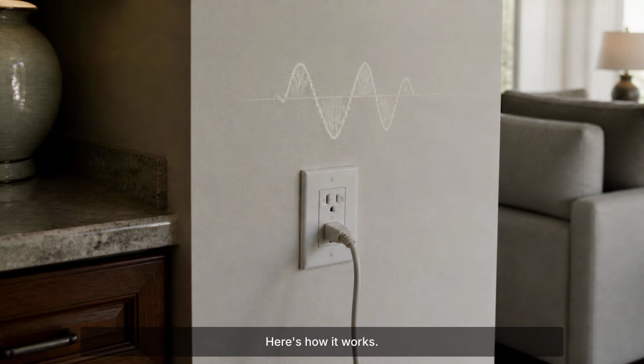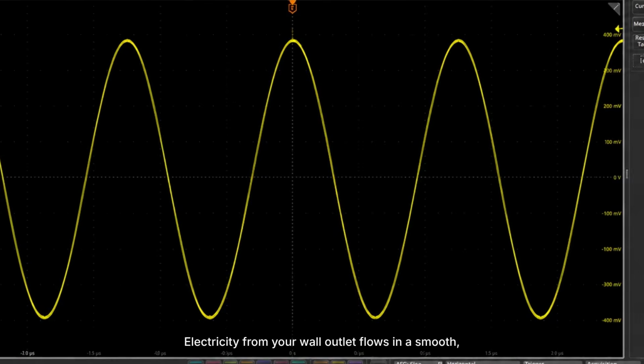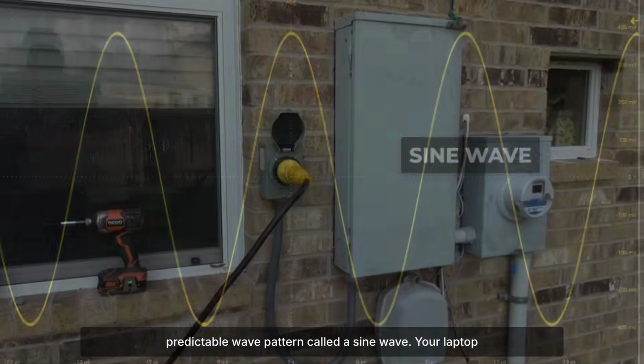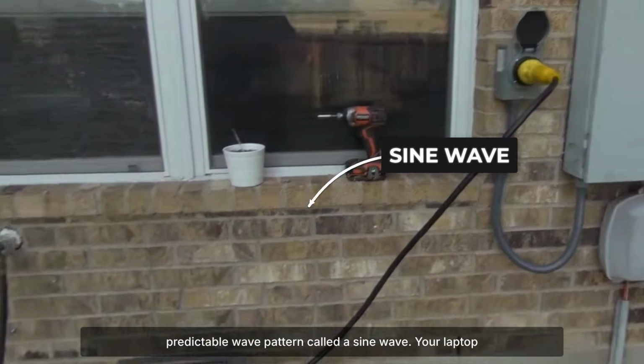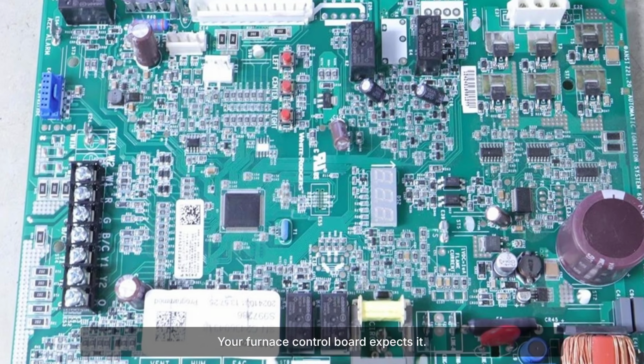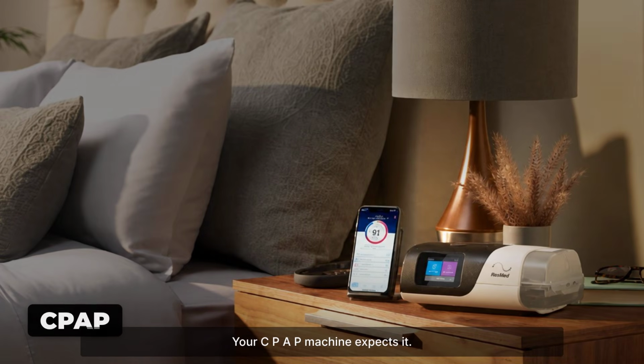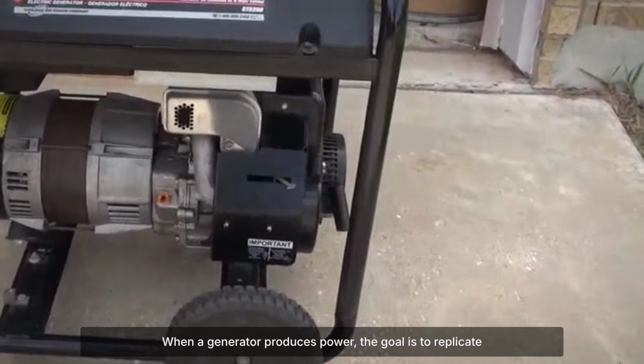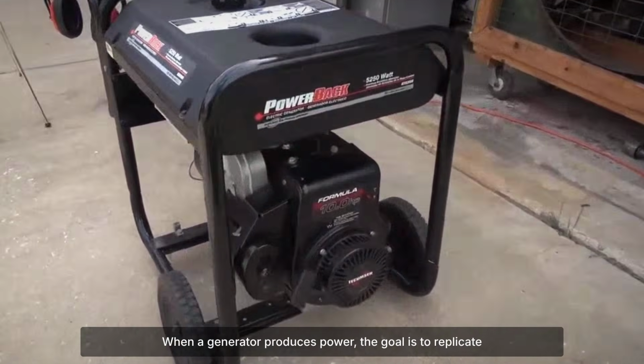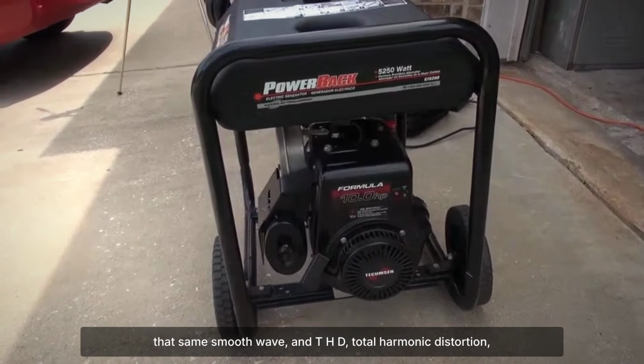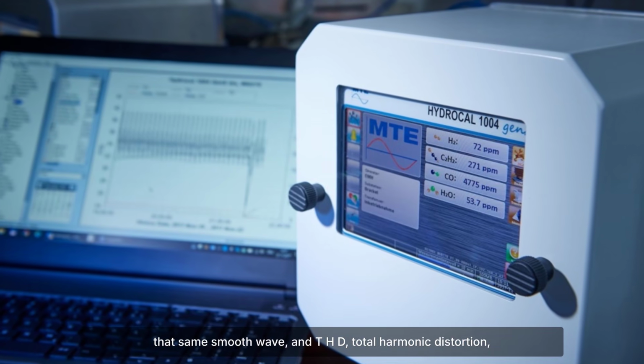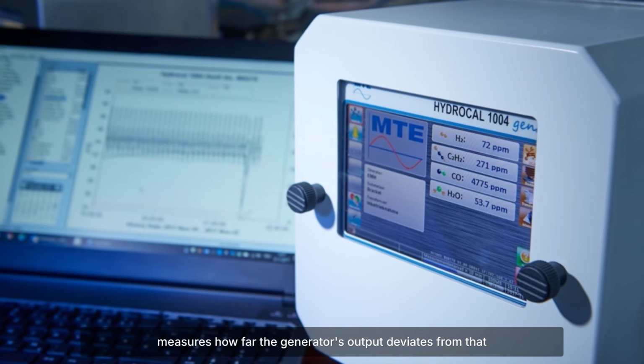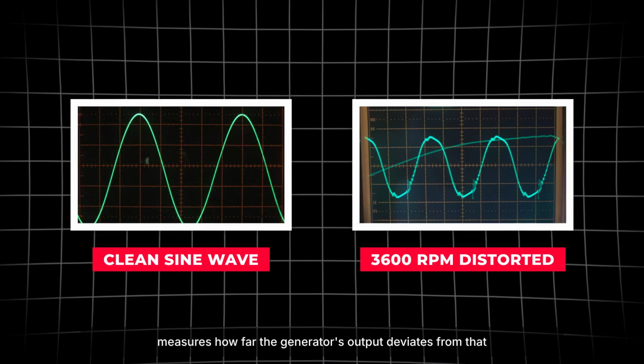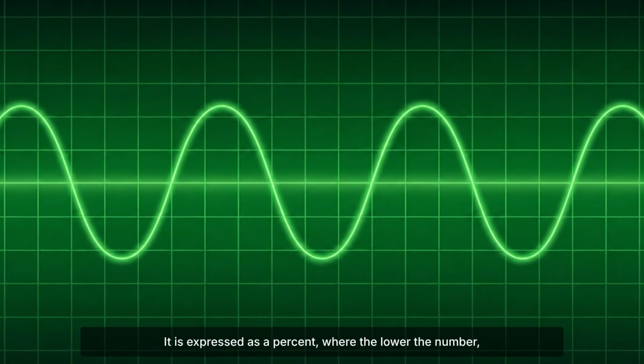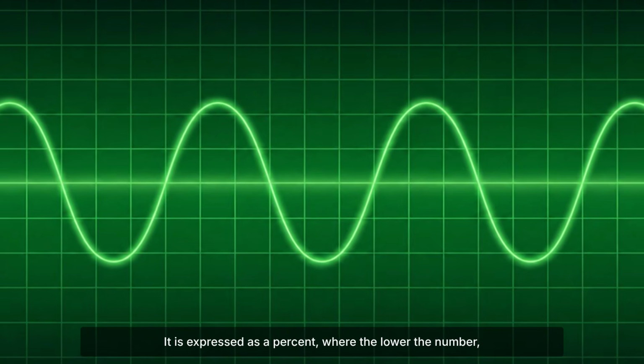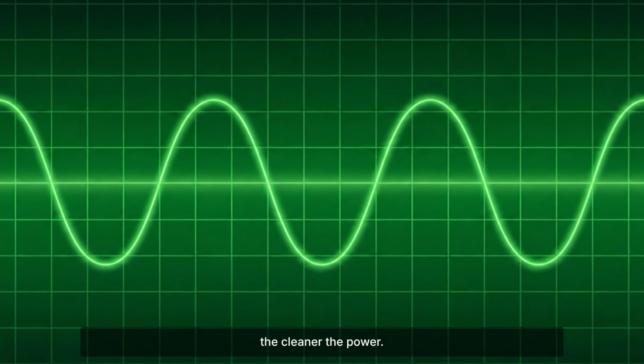Here's how it works. Electricity from your wall outlet flows in a smooth, predictable wave pattern called a sine wave. Your laptop expects it, your furnace control board expects it, your CPAP machine expects it. When a generator produces power, the goal is to replicate that same smooth wave. And THD, Total Harmonic Distortion, measures how far the generator's output deviates from that ideal. It is expressed as a percent, where the lower the number, the cleaner the power.